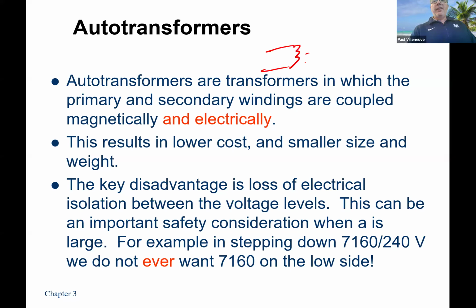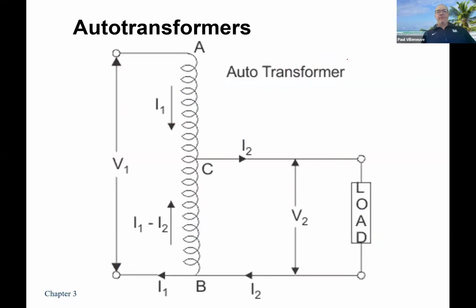An auto transformer does this, and these windings are connected like that. So technically, there isn't even a winding here. It's almost like a tap position off there, so it just drops the voltage. Auto transformers are very cheap because you only have really one winding, but you don't have electrical isolation. So they can make it very difficult. But you can have auto transformers that can step up or down very efficiently. But again, remember we talked about how we don't want an auto transformer going to our house, because if a fault occurs, you could have live 7160 in your house. Not a good thing to do. That's a picture of the auto. That's it.